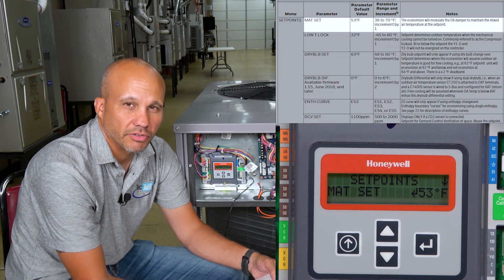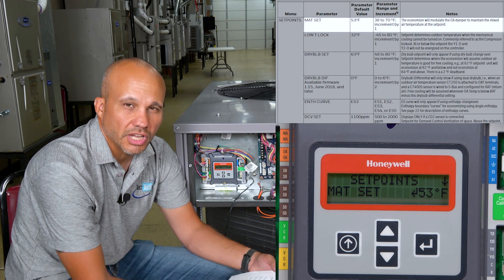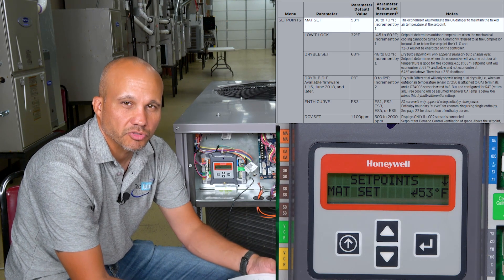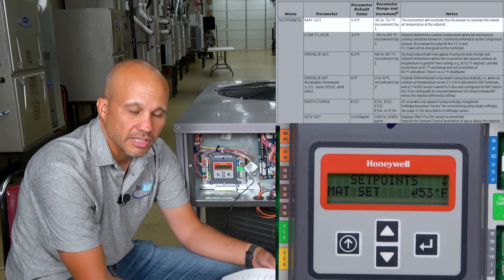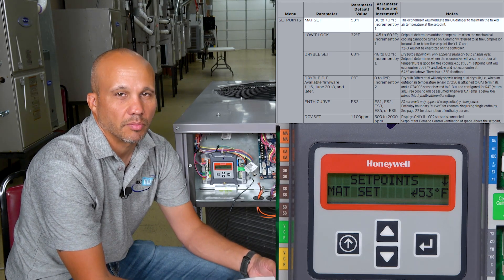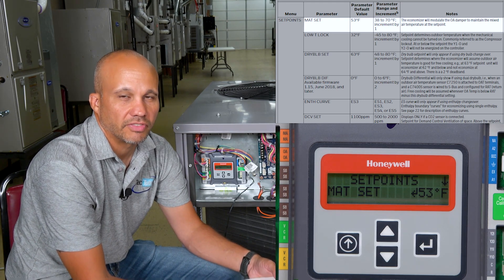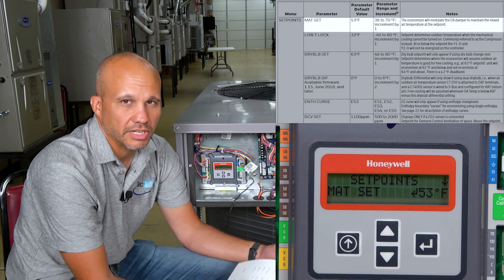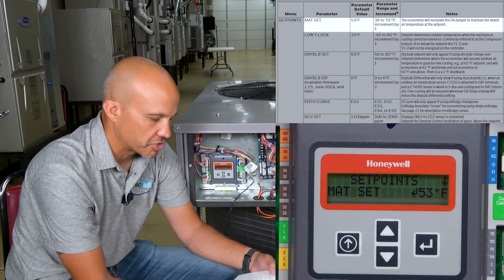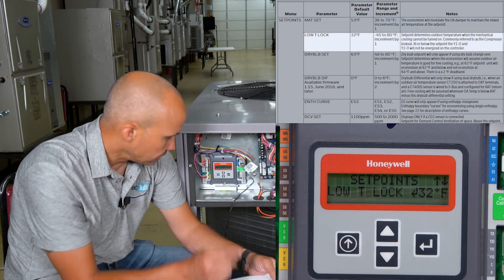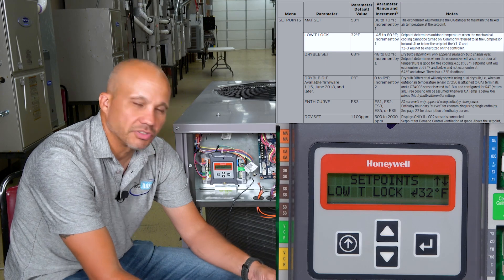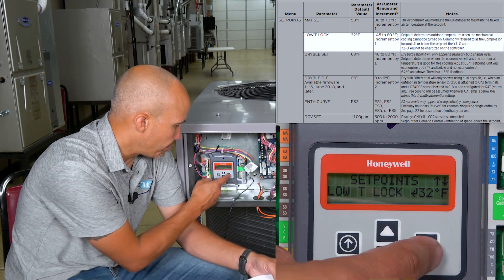The default Mixed Air Temperature Set Point is 53 degrees — that's pretty normal. Systems are designed for 55-degree supply air; the sensor is upstream of the fan, and the fan adds a degree or two of waste heat, hence the 53-degree set point. You'll leave that alone for a regular job. If you had a weird project doing something special, you might change it, but 53 is the right number.